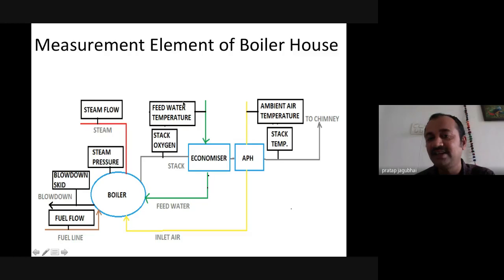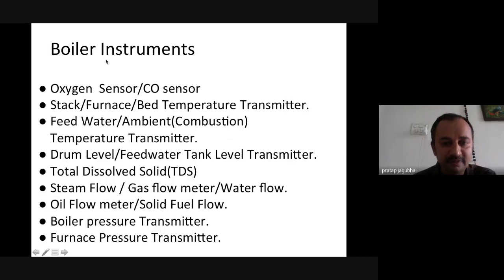And so you can easily see what kind of instruments will be required. The instruments will measure temperature of water, combustion air and flue gas, oxygen in the stack, and stack temperature. Then the flows: steam flow, water flow, fuel flow, and the pressure and the blowdown TDS. All these put together make up our boiler instrumentation, comprising what is required to be controlled. Just a glimpse of the list of components identified from that elementary model: the most important is combustion oxygen measurement. Indirectly we can also control CO, by maintaining the oxygen, to some extent.